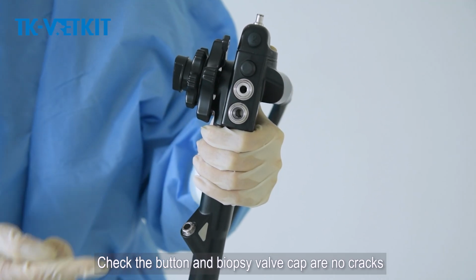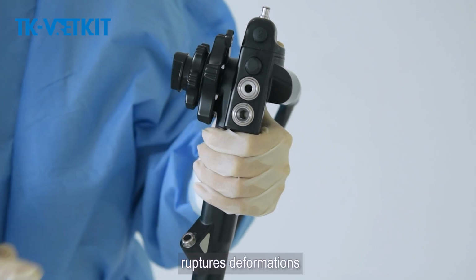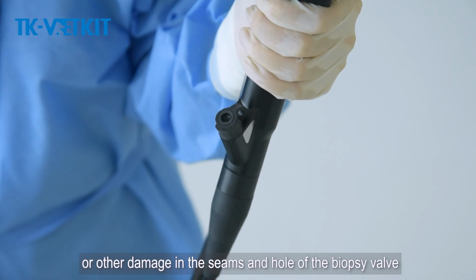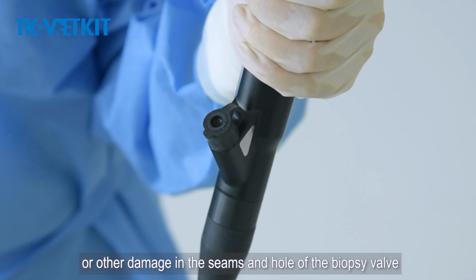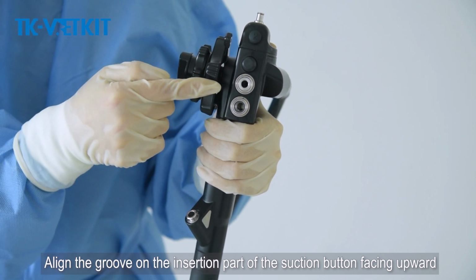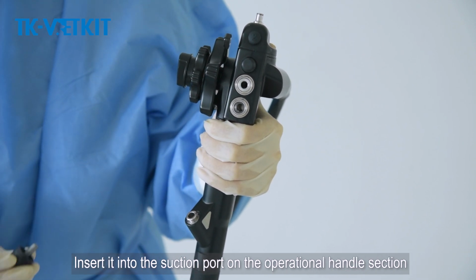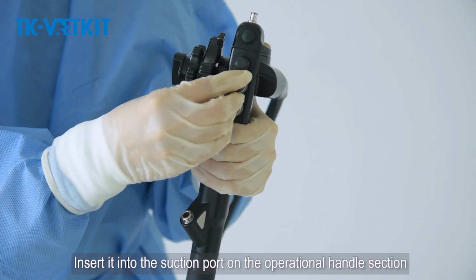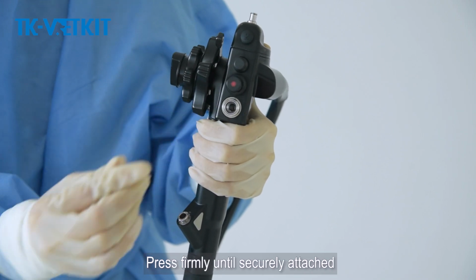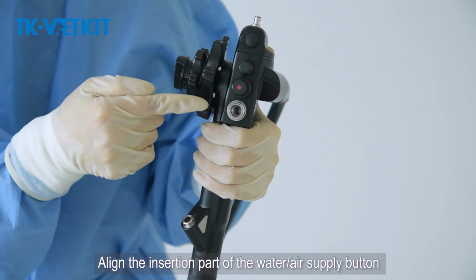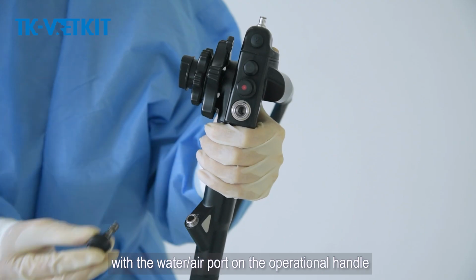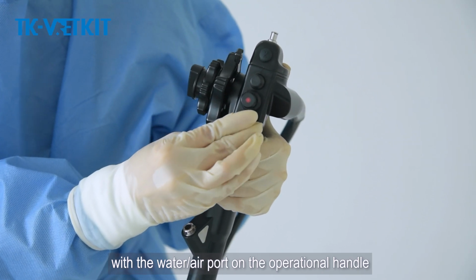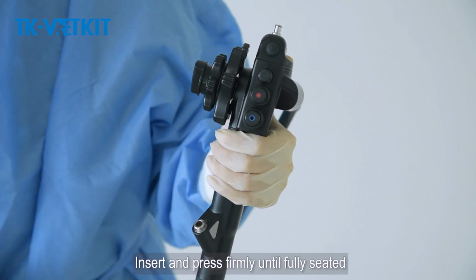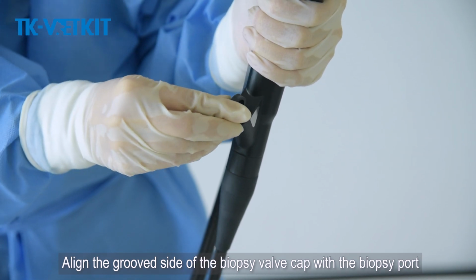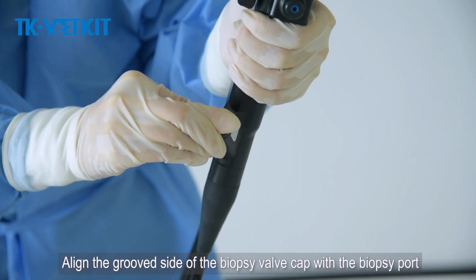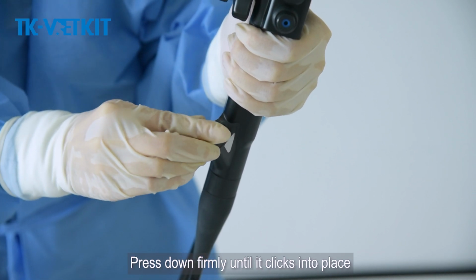Check that the buttons and biopsy valve cap have no cracks, ruptures, deformations, or other damage in the seams and hole of the biopsy valve. Align the groove on the insertion part of the suction button facing upward, insert it into the suction port on the operational handle section, and press firmly until securely attached. Align the insertion part of the water/air supply button with the water/air port on the operational handle, insert and press firmly until fully seated. Align the grooved side of the biopsy valve cap with the biopsy port, and press down firmly until it clicks into place.